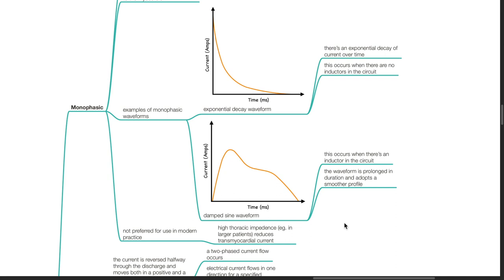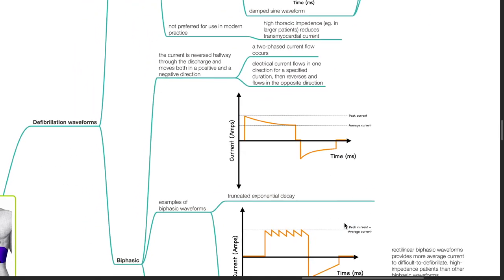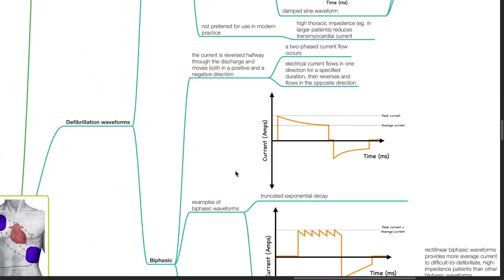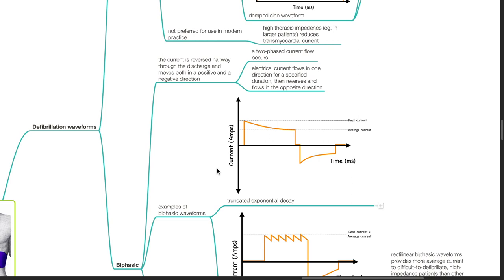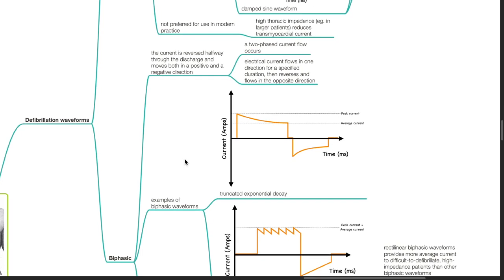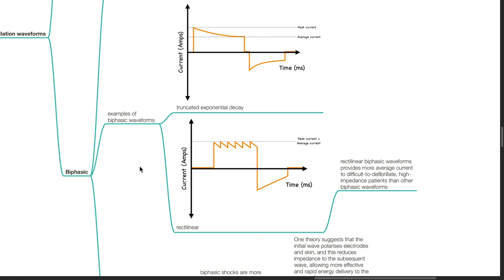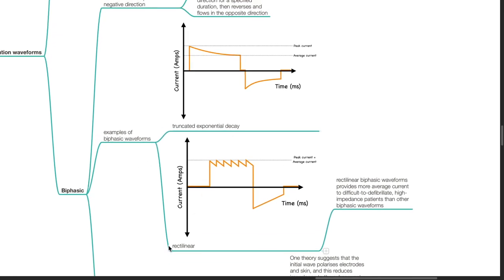High thoracic impedance, such as in larger patients, reduces transmyocardial current when monophasic waveforms are used. Biphasic waveform: the current is reversed halfway through the discharge and moves in both positive and negative directions. Electrical current flows in one direction for a specified duration, then reverses. Examples include truncated exponential decay waveform and rectilinear waveform. Rectilinear biphasic waveforms provide better average current delivery to difficult-to-defibrillate high-impedance patients than other biphasic waveforms.